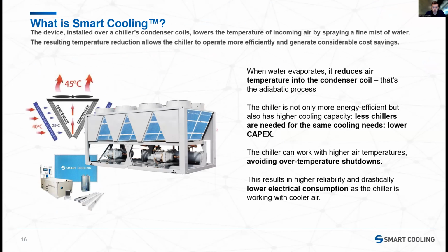So what does that mean in simple words? It means the lower the ambient temperature reaching an air-cooled chiller, the more efficient it is in terms of electricity — lower electrical consumption and more cooling capacity. To give you a rough idea, on average across chiller manufacturers, every 1 degree increase in ambient temperature causes the chiller to lose about 2% of efficiency. So combined, that's more electrical consumption and less cooling capacity.